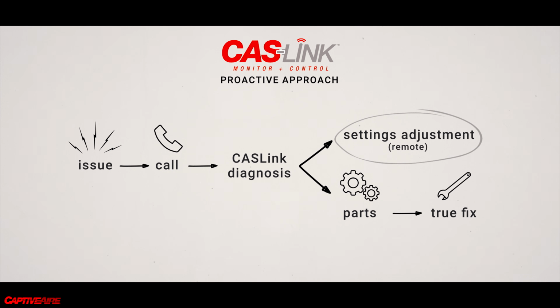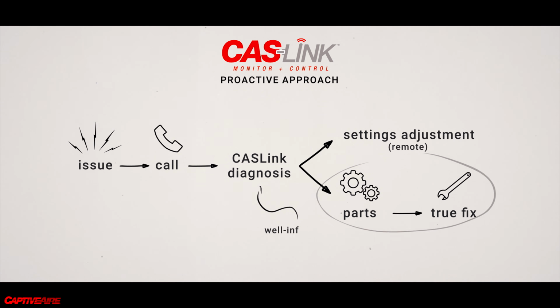What we want to do is, all right, if we have an issue, we want to see it in real time, go back and see what led up to that actual fault. And then from that, we can either find out if it's a setting adjustment that needs to be done, which is a nice simple thing we can do remotely without even sending somebody out there. If it is something that's hardware based, it gives us an idea of, all right, it looks like this sensor or this component has failed.